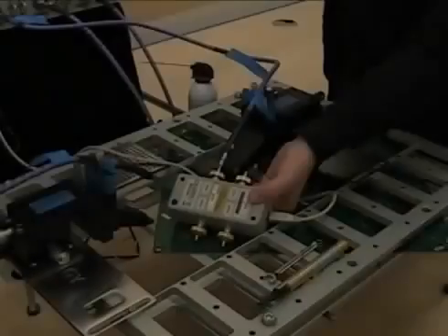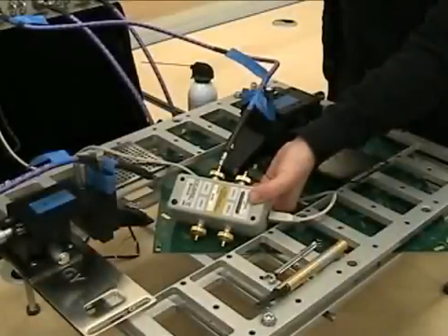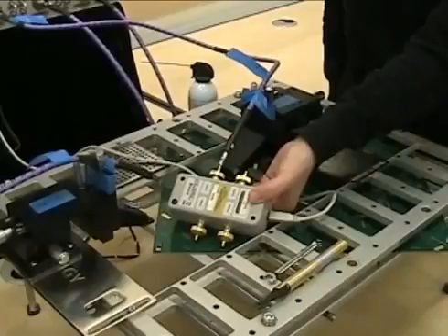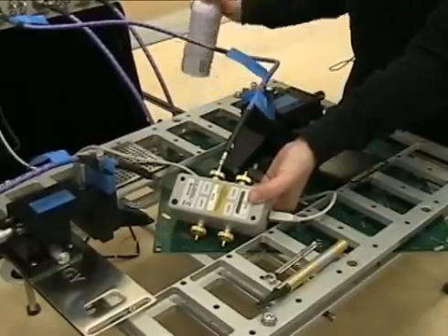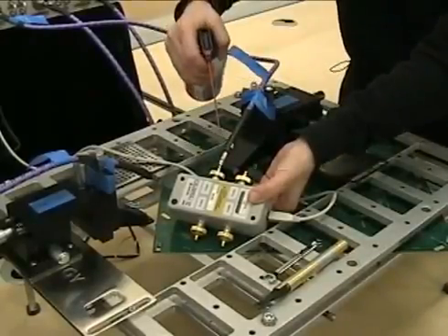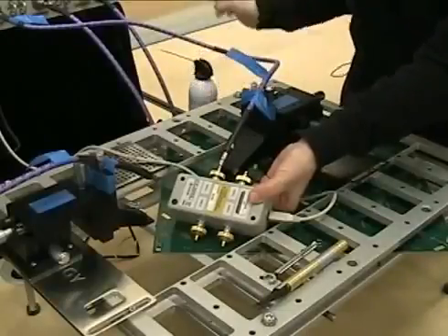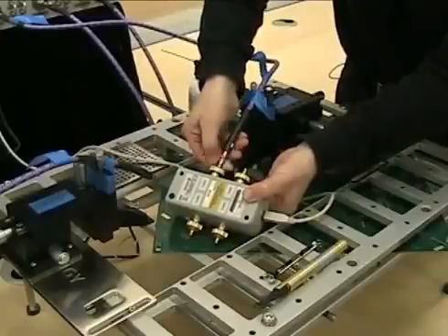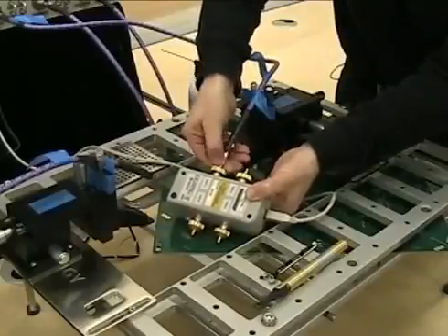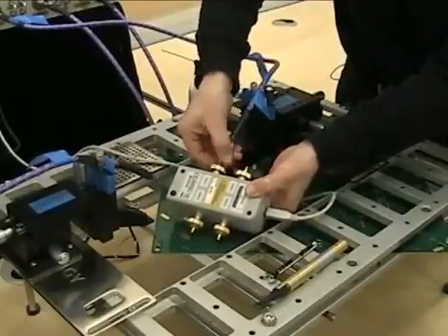time domain. When connecting the electronic calibration module to the network analyzer cables, it is important to follow some general connector care requirements. Here you can see we blow off the connections before mating them. The precision connectors should be easily connected together with finger tightening.